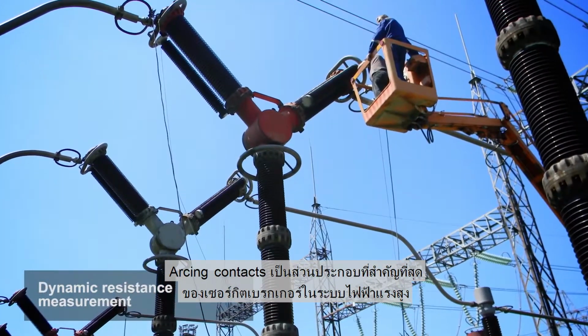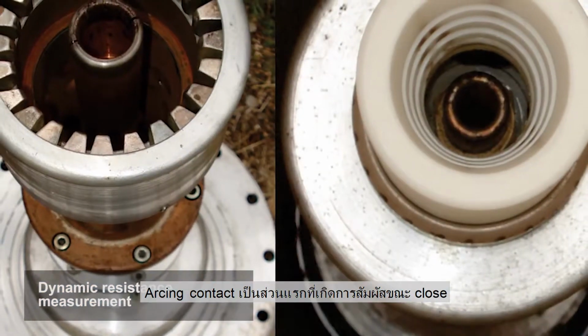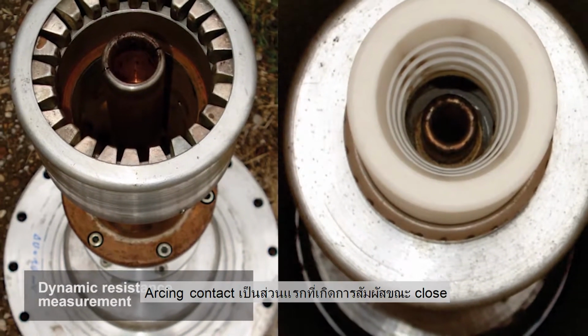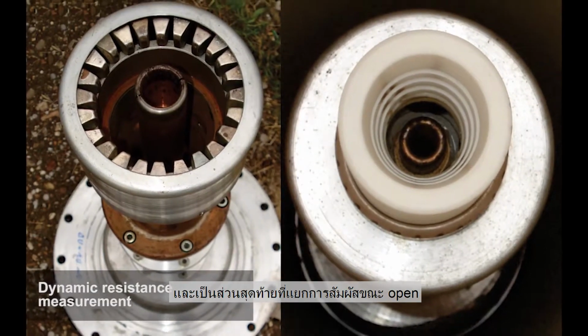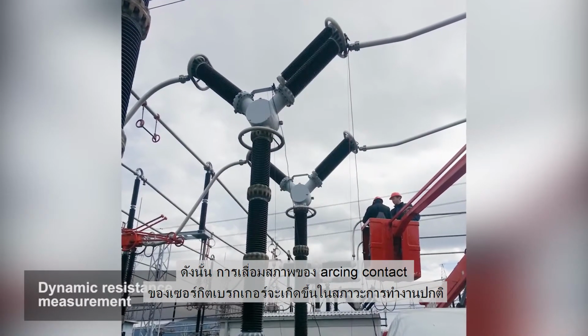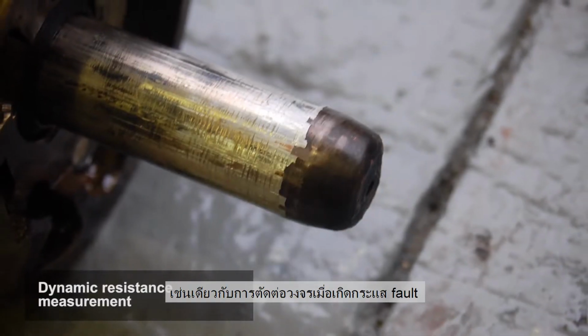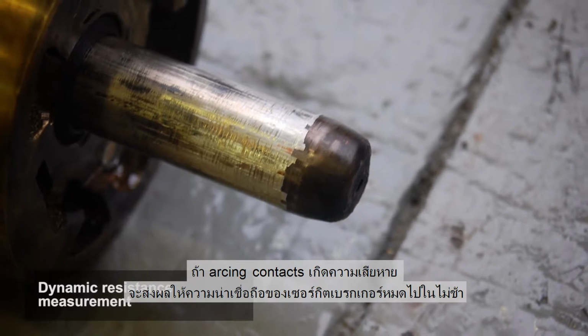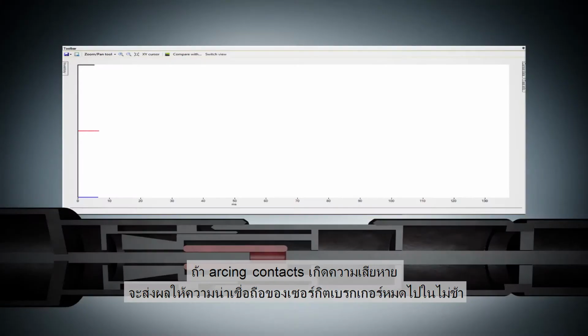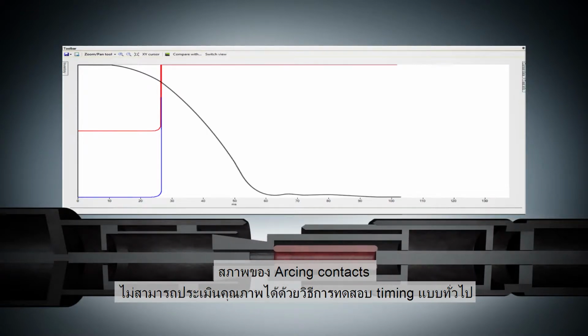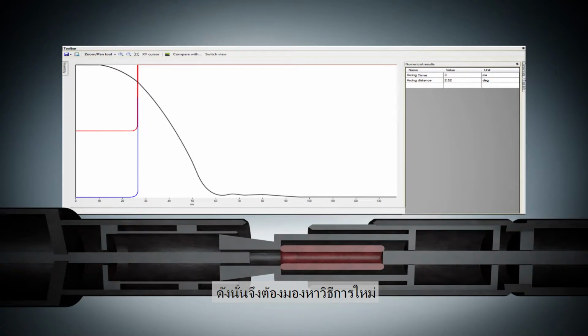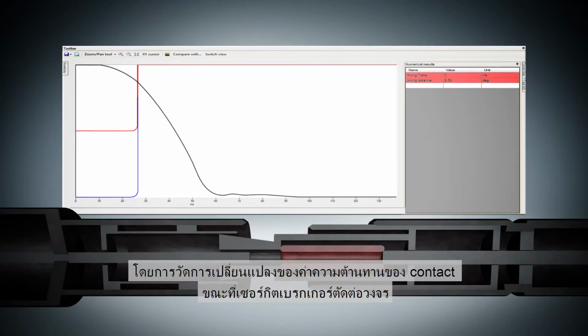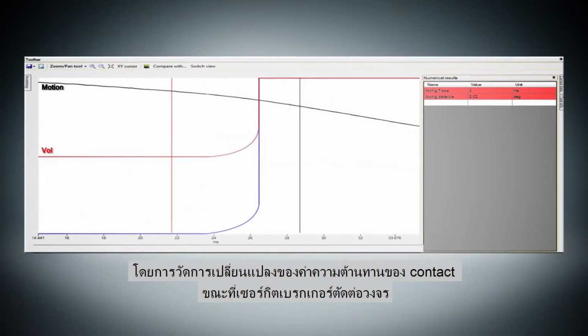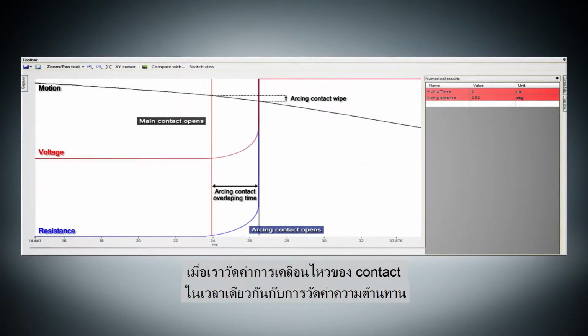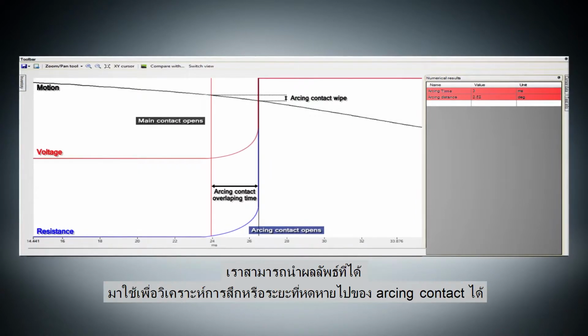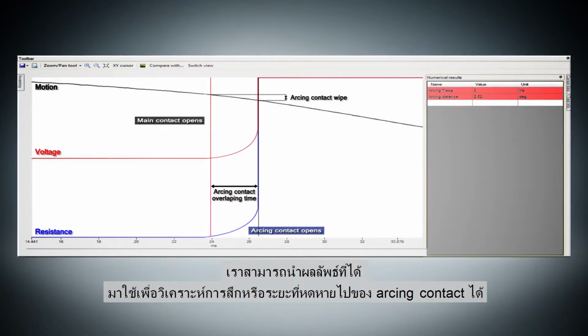Arcing contacts are the most important parts of the high voltage circuit breakers. The arcing contact is the first to make contact during a closing operation and the last to break contact during opening. Therefore, circuit breaker arcing contact wear occurs during normal operation as well as when interrupting fault currents. If the arcing contacts are damaged, the breaker becomes unreliable very soon. Arcing contact condition cannot be assessed by conventional timing tests, so a new method has been looked into. The dynamic resistance measurement method measures variations in the contact resistance during the breaker operation. When the breaker contact motion is measured simultaneously with resistance, the results can be used to assess the wear or reduced length of the arcing contact.